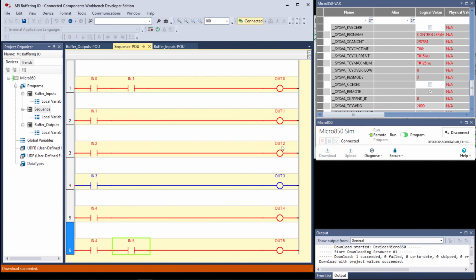These colors displayed represent on or off. In other words, the fact that this is red and it's on, what if we put in a true if off instruction? It would be false when that input is on, correct? So over here, make sure you're thinking true and false, never on or off. Over here, what is displayed color-wise is on or off. As I said, some have a true execution and a false execution, like the direct coil. Some have just a true execution and no false execution. Some have a false execution and no true execution. And I will show you those in later labs.